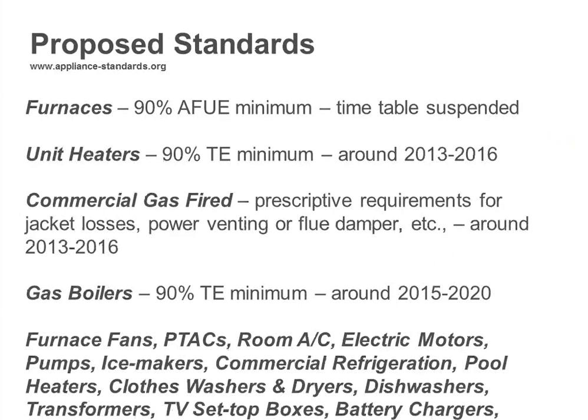There's a bunch of other stuff that's set to change via the Department of Energy manufacturing rules. The furnace stuff, as most of you know, is kind of on an indefinite hold, so we'll update you on that as things change. Boilers are slated to get another efficiency boost, furnace fans, PTACs, room units. There's all kinds of stuff kind of on the schedule there. The best website to go to is appliance-standards.org, and they track each appliance individually and what its current legal status and timetable are.